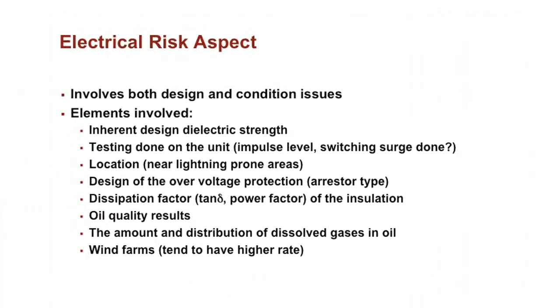And then also what level it was tested at. In the standards, if you're looking at impulse voltage, there are normally three or four ranges it could be designed for, and this is given by whoever is buying the transformer. For example, if it's designed for a 650 impulse, it could also have been designed for 550 or 750 or 850. That's important to know, also relative to where it is in the grid. The location matters, as there are some places in the world that are much more lightning prone. Florida is, I think, one of the highest in the world. So being located in Florida versus a less lightning prone area makes a big difference as well.